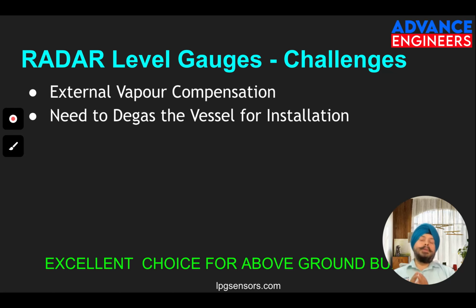So what we do is provide a full bore ball valve installed on the radar - only then will it work. Now if that ball valve isn't there, or you don't have a proper valve with full pass through, then we need to degas the vessel.